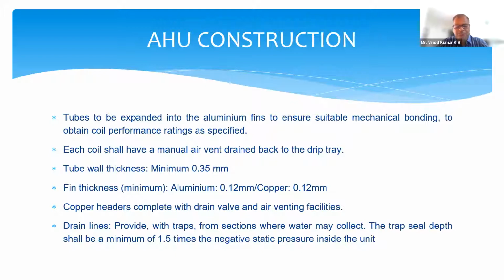Now here the drain pipe has to have a proper U-trap. The trap selection is also very important, because if the trap is not selected properly, the water inside the drain pan will never get drained. And if it gets stuck in the drain pan for long, the air takes the water and puts it into your laminar plenum where the HEPA is. So it's important that each AHU has a drain pipe with a U-trap. The size of the trap is calculated with a minimum of 1.5 times the negative static pressure.